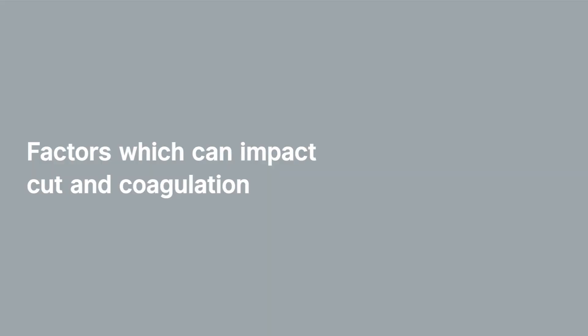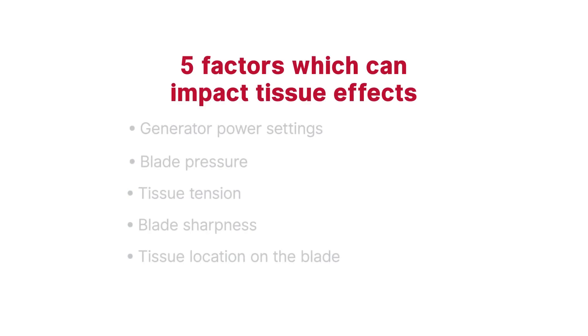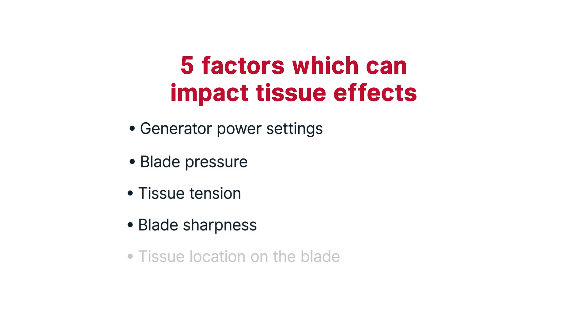There are five factors which can impact tissue effects with ultrasonic devices. Increasing or decreasing these settings influences the balance of coagulation and cut: generator power settings, blade pressure, tissue tension, blade sharpness, and tissue location on the blade.